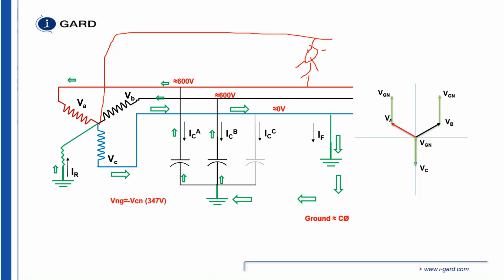your electrician, when changing the ballast on a 347 volt light, is going to lock out and tag out the switch that takes the light out of service. He's going to measure the voltage phase to phase and phase to ground, determine that it is de-energized, lock it out, tag it out, start changing the ballast. But then what would happen is if you get a ground fault on C phase, anywhere in your facility, that neutral voltage can elevate to 347 volts above ground. And that poses a shock hazard. So that's why it's unsafe, I believe, to have a distributed neutral on a high impedance grounded system.